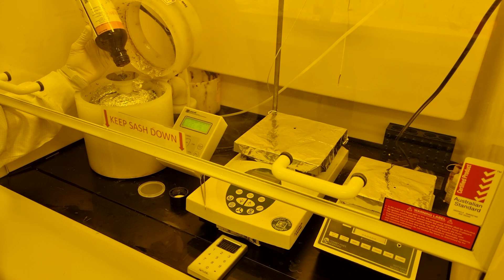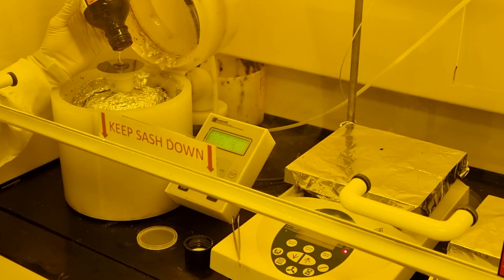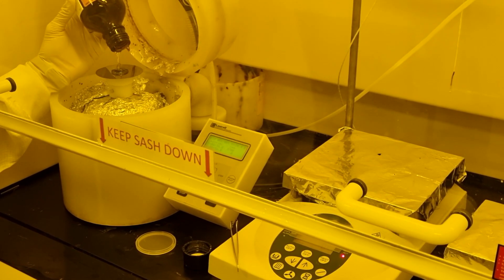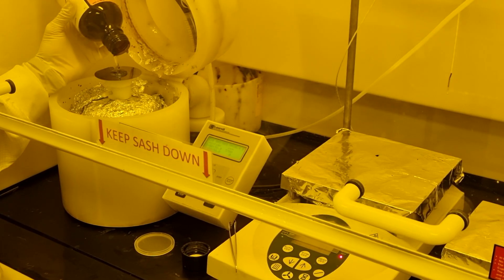Programming the spinner is not obvious. There is a procedure posted above the fume hood. Once you think you've got the spinner settings right, test them on a blank substrate before loading your wafer.